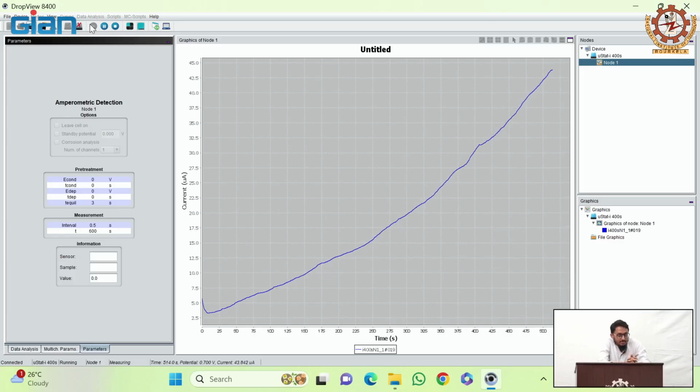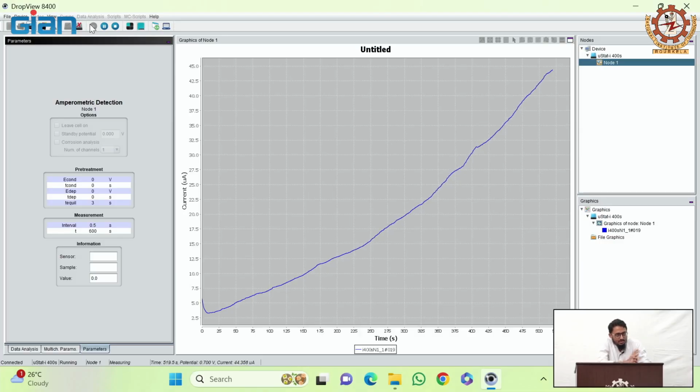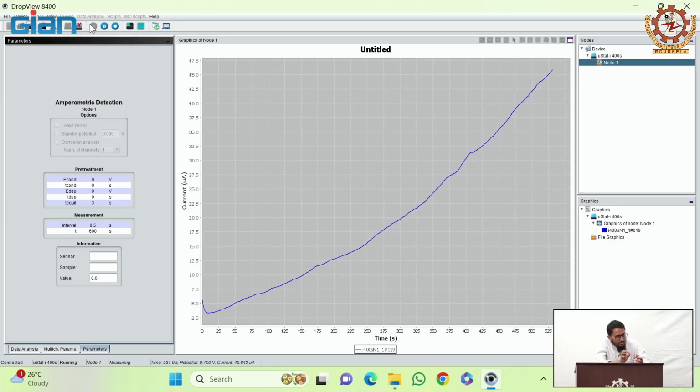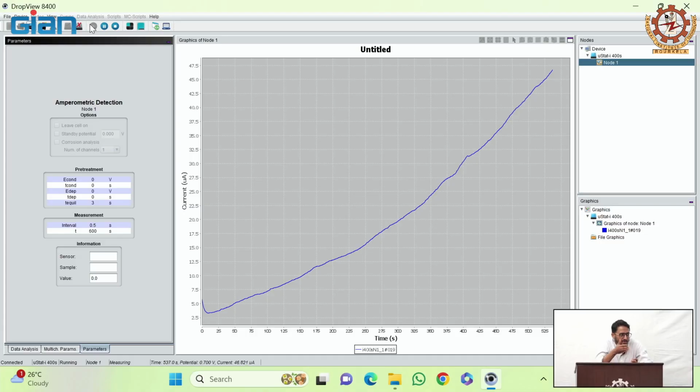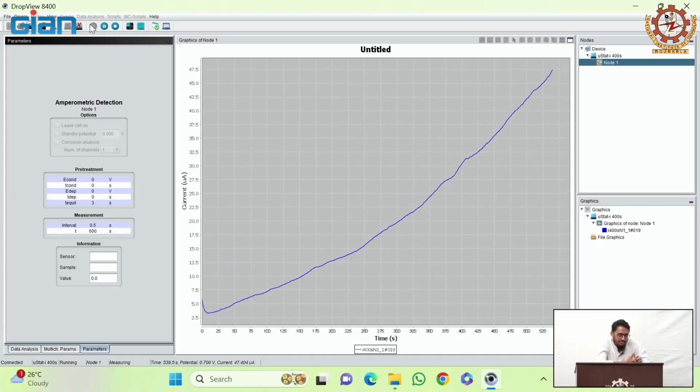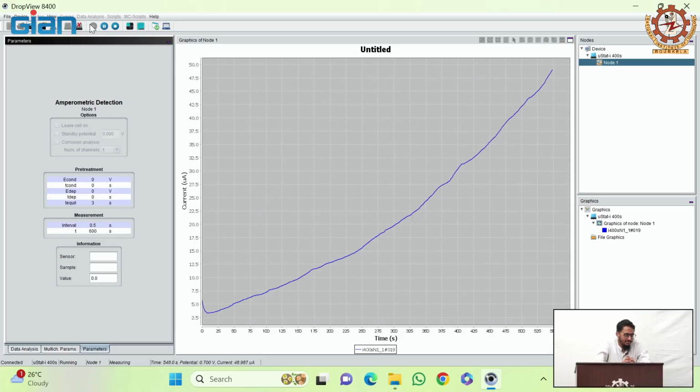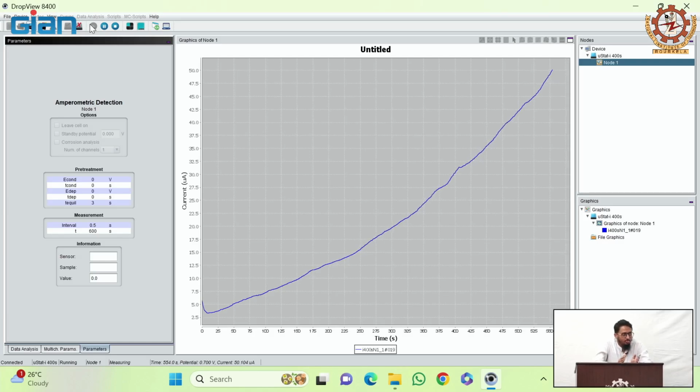Okay, so these sensors nowadays are factory calibrated sensors. Previous CGM sensors, there are a couple of companies which wanted their patients to calibrate the CGM in a way that they will ask them to do a finger prick reading, draw the blood, measure using a glucometer and enter that value in their app. So they will do the adjustment there. But nowadays, because it is inconvenient for the patient to take the reading twice, and it kind of defeats the purpose of using a CGM sensor, because anyway we are doing this spot measurement again, more and more the trend is towards factory calibrated sensors, where you don't ask the patient or the user to do frequent calibrations.